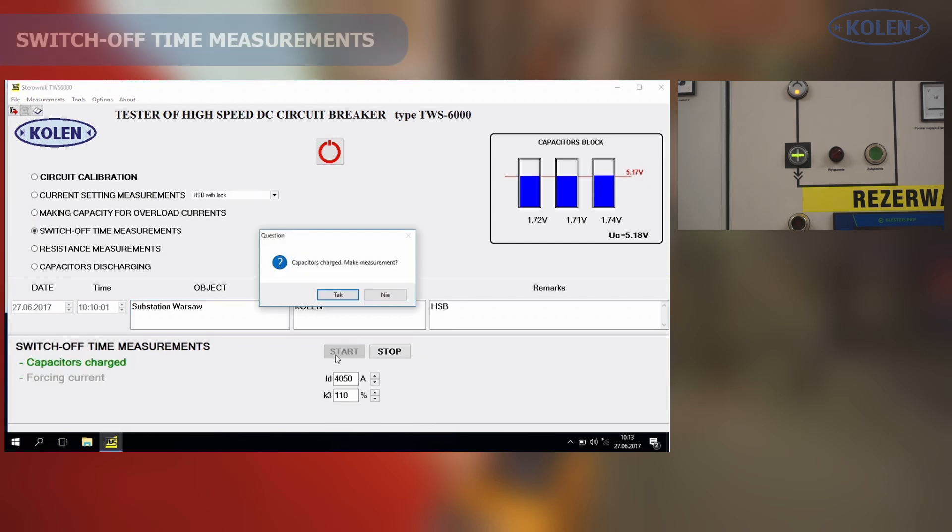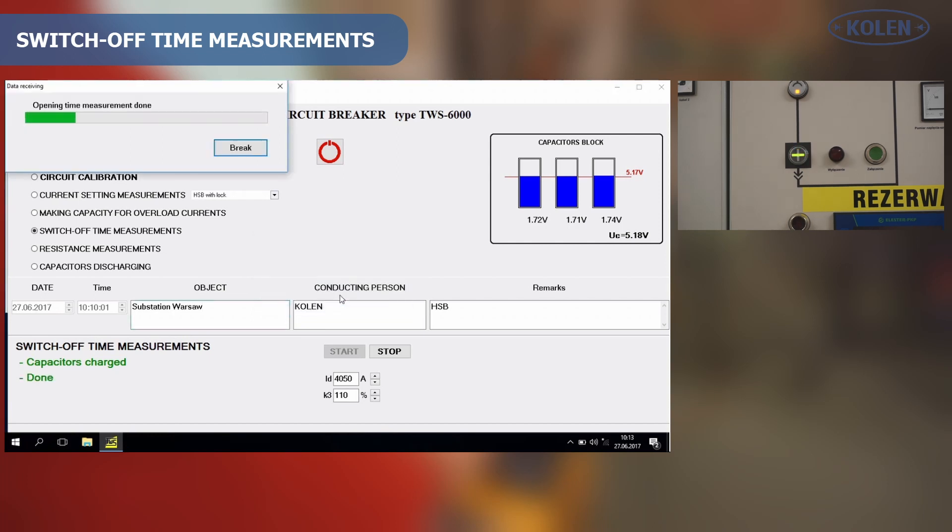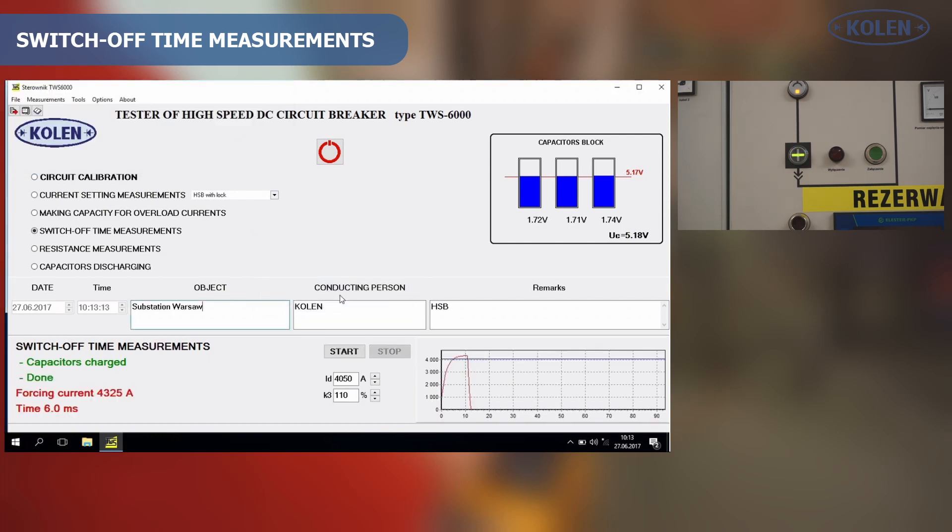The measurement of HSB switching off opening time performed by TWS is not defined in any norm, but based on obtained test results, HSB technical condition can be evaluated.